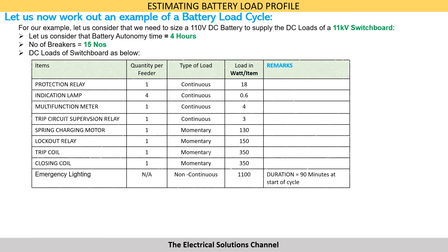Let us now work out an example of a battery load cycle. We have to size a 110 volt DC battery to supply the DC loads of an 11 kV switchboard. The battery autonomy time is considered as 4 hours, and the number of breakers in our example is 15. The DC loads of the switchboard are as given in the table.